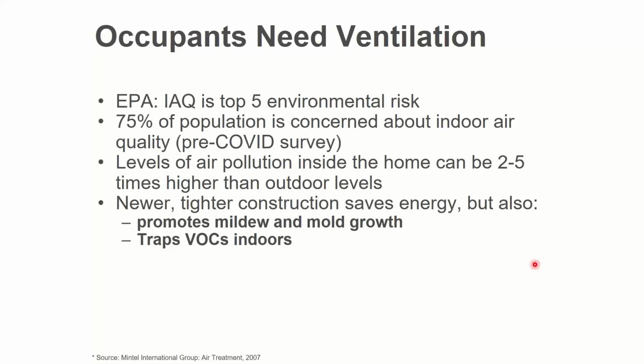Now, I don't need 100% outside air. I can have some recirculation, and in fact, I will, because if I bring 100% outside air in, which means 100% exhaust, the air comes through my building one time. If I did that, it would be extremely expensive to heat and cool my building. So I'm going to be bringing in, depending on your building, and we'll talk about some different ways to figure that out, 5, 10, 15, 20, 25, 30% outside air, right? Normal buildings are going to be between 10 and 30% of their air comes from the outdoors, which means that 70 to 90% of the air is recirculated. And if I do that throughout the course of the hour, I'm going to get enough air changes that it's going to be, you know, code acceptable and desirable.